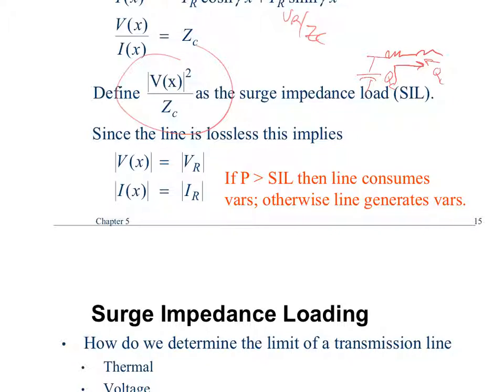So there's no voltage drop, right? R is equal to 0. The plus-minus voltage drop is 0 here because all the reactive power the line needs is being provided by the capacitor bank, so there's no voltage drop across the line. And since there's no net current lost here, the VARs being consumed are matched by the VARs provided, so the current is exactly the same through the line. The magnitude of the voltage and the current is uniform across the entire length of the line.